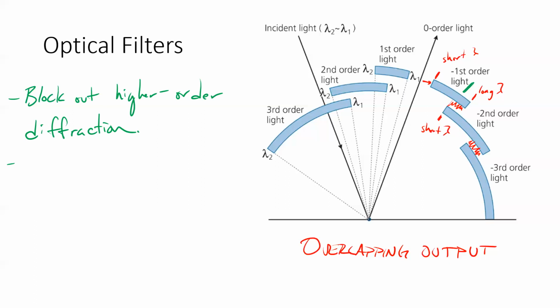Can they detect that? How does that work? So it's not a detected thing, it's just an engineering thing. Engineers say, okay, in this particular instrument setup, that overlap starts happening when our first order diffraction is at 535 nanometers. And so we're going to have a filter that pops in when somebody's measuring above 535 nanometers.